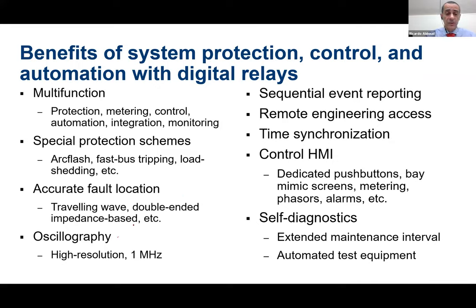In terms of event reports and oscillography, with the digital relays we can have high resolution event reports with a sampling rate of 1 megahertz. So you can detect problems related to fast transients in the power system. For instance, the transient recovery voltage, which is a really big problem for circuit breakers, or reignition and restrikes for circuit breakers. With a conventional low sampling rate, we cannot see that, but now we can see that, okay? SER, sequential event reporting or sequence of events, is another important feature available in the relays.